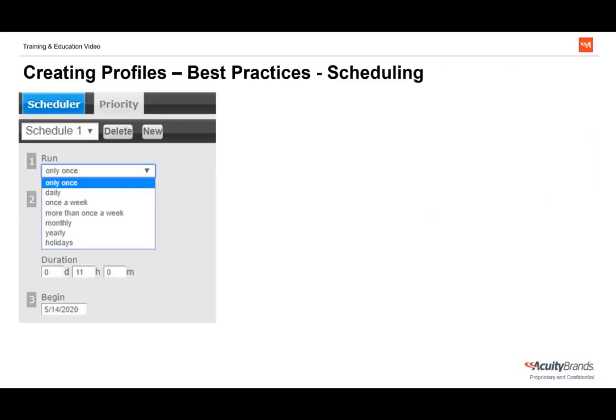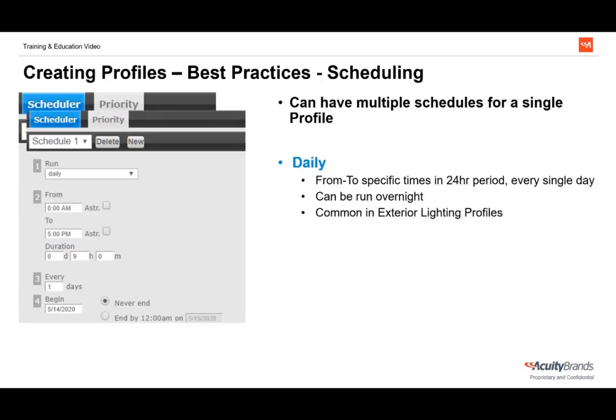Now that we've figured out how to set up our settings, we can move on to building the schedules. There are many types of scheduling methods available, and we can have multiple schedules for a single profile. Daily schedules run every single day, including Saturday and Sunday, and can run overnight. Be careful — if a daily schedule ends on the weekend, you'll need to use once-a-week schedules if you want a profile to run all weekend.